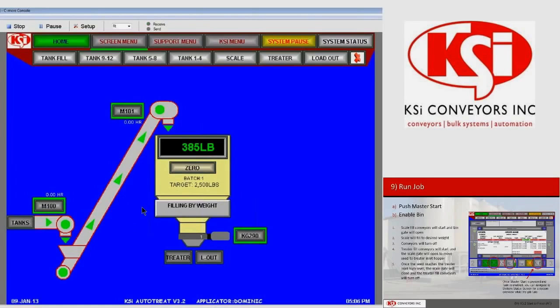Again, it's going to close the bin gate when it hits the target weight minus the preact being about 300 pounds. So at 2,200 pounds, the bin gate will close, and we'll see this filling by weight change over to conveyor clean out. Okay, we're approaching 2,200. As you can see, when we hit that mark, the conveyor went into clean out, and the conveyors are going to run for 18.1 seconds. At the end of that 18.1 seconds, the conveyors will turn off, and our scale should read 2,500 pounds, which was our target. There goes our conveyors turning off.